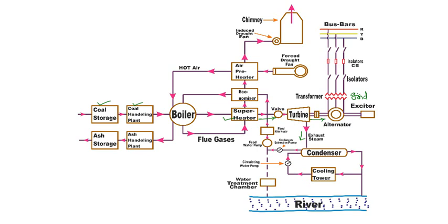After that, it goes forward to the feed water pump, then the feed water heater, which increases the temperature of the water, and so the temperature level of the steam, increasing the efficiency of the steam power plant. This method of taking steam out from the turbines to heat the feed water is called bleeding of turbines, which increases the overall efficiency of the boiler.